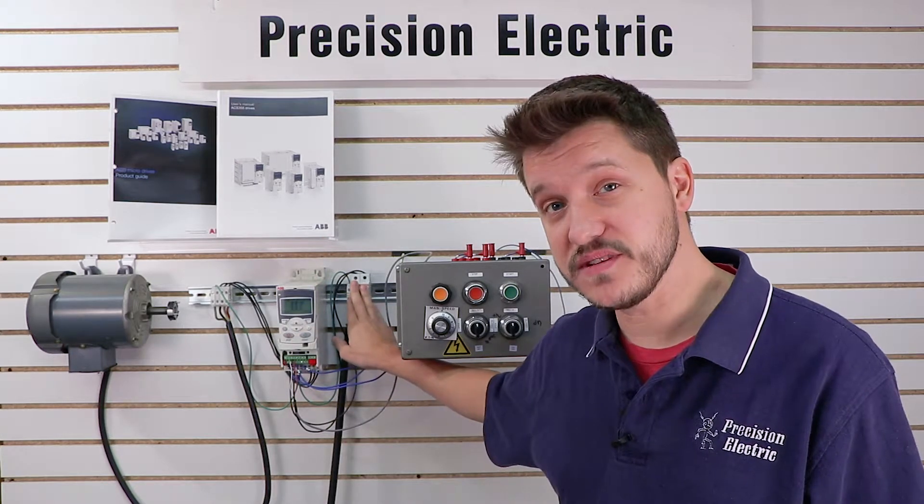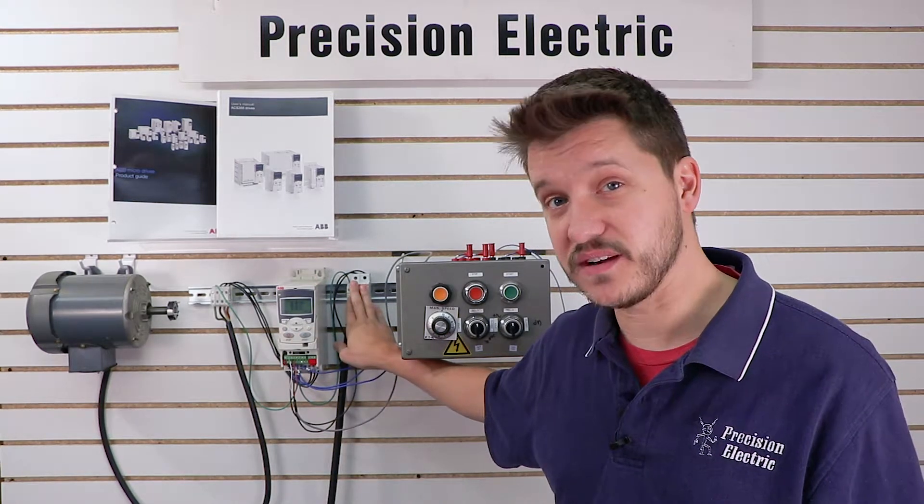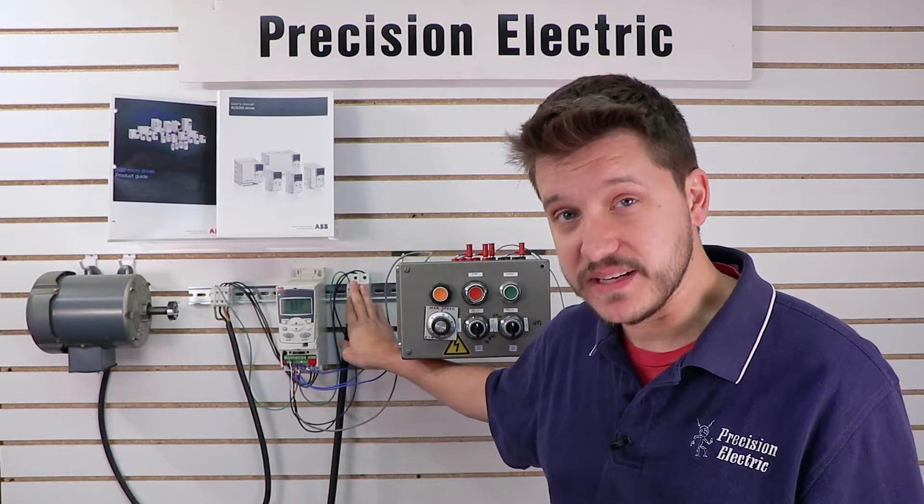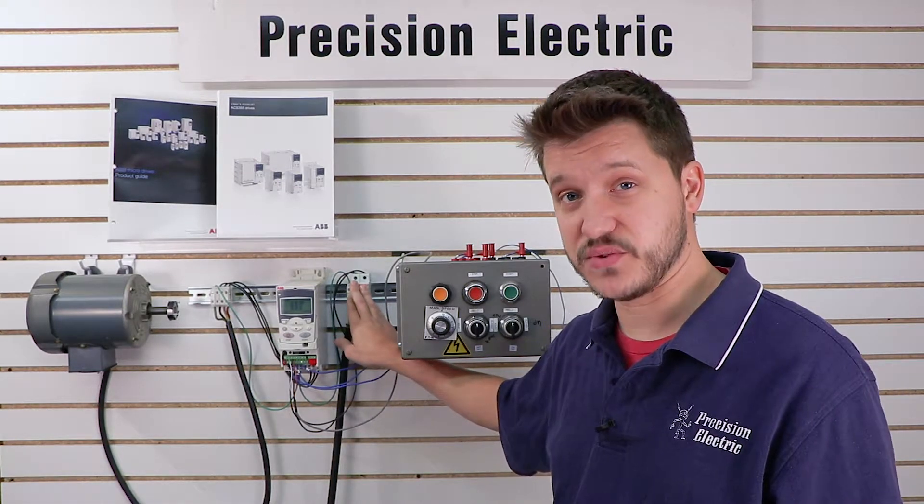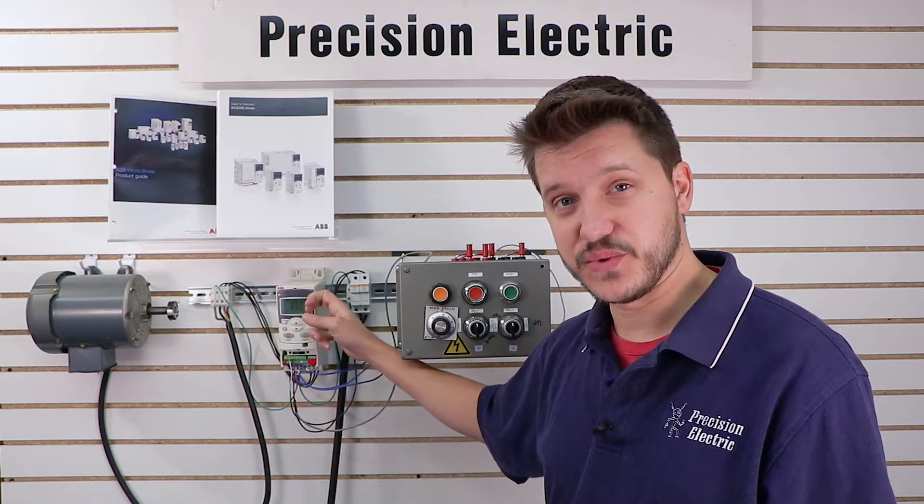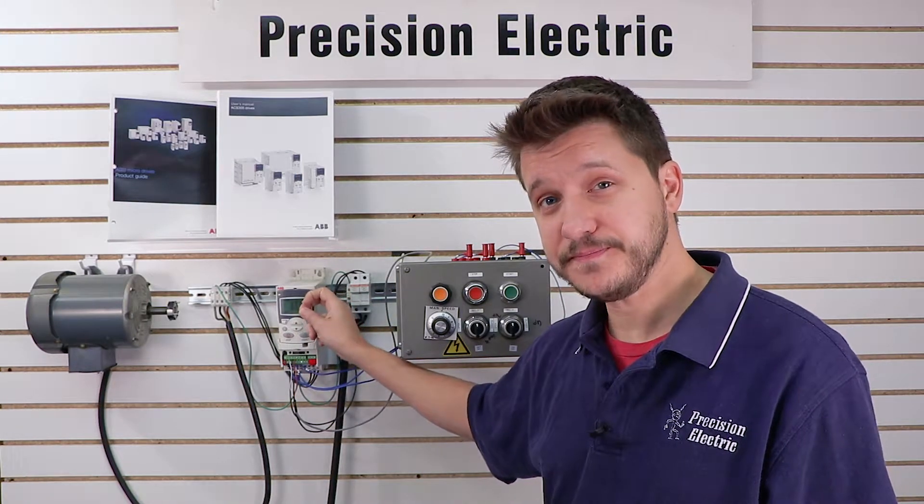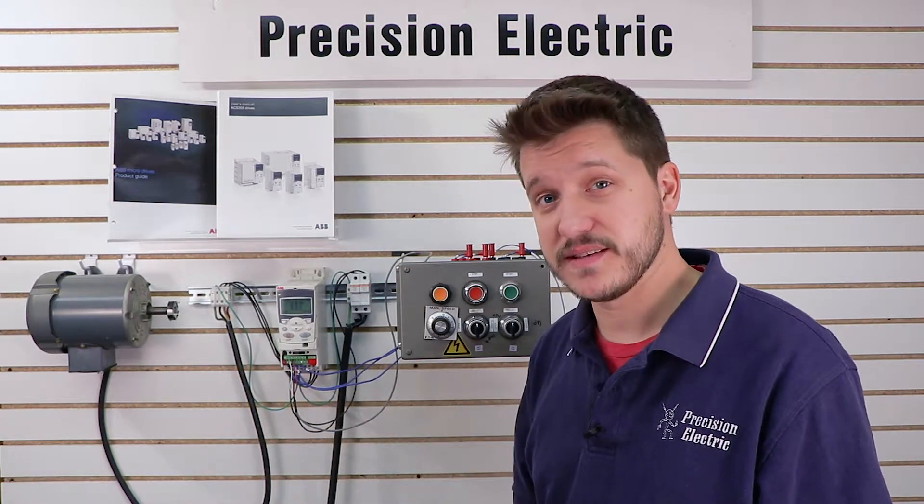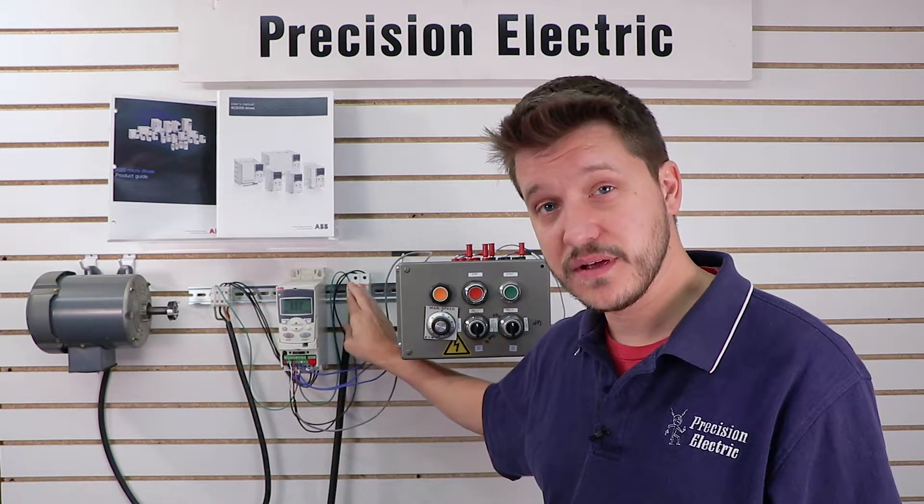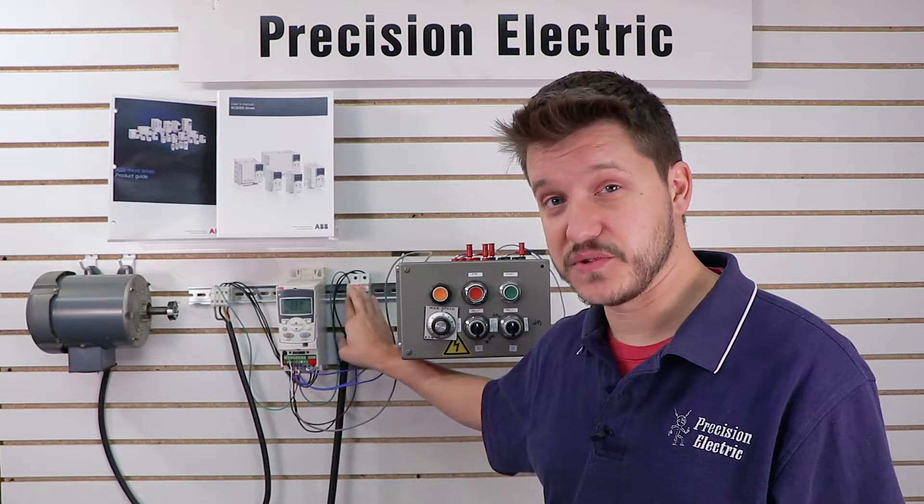As for type of fuses, you can obviously use a circuit breaker. That's our least recommended option because circuit breakers tend to have the longest delay between tripping. So you most likely have a situation to damage the drive because that time frame it takes to sense the current and then trip is a lot longer than a fuse.